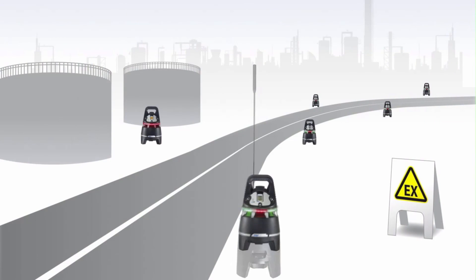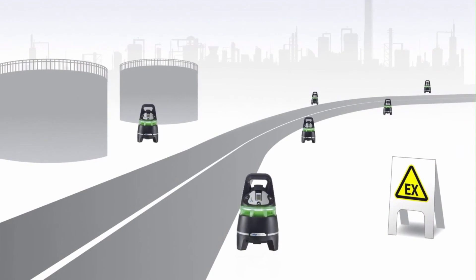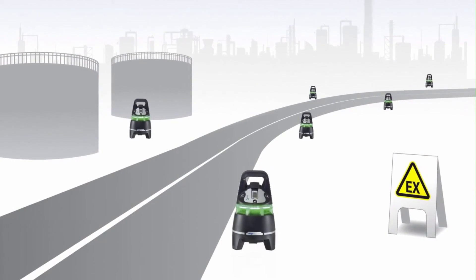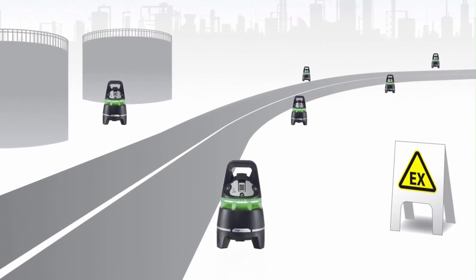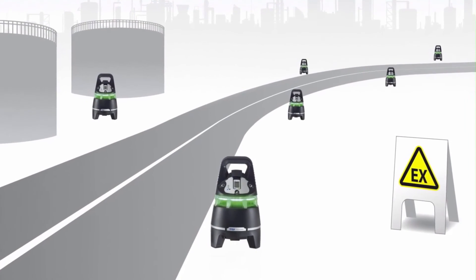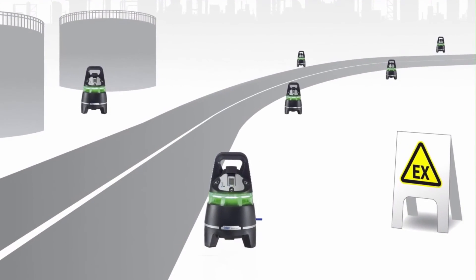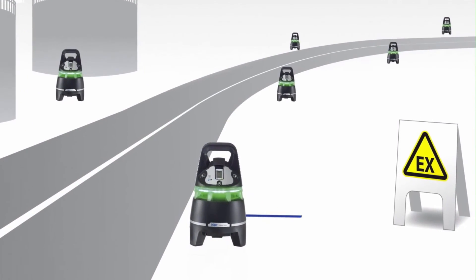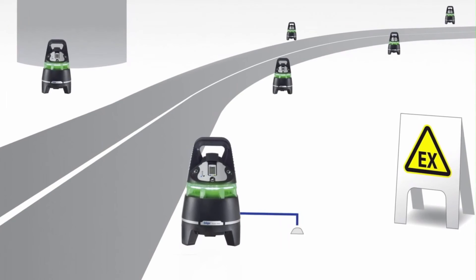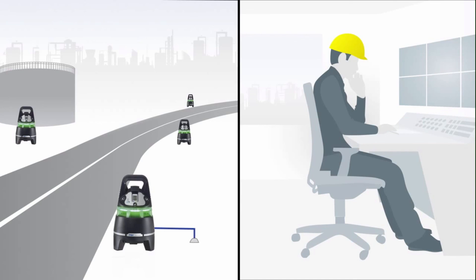You can also integrate X-Zones into your existing gas detection system. Every X-Zone has a Modbus interface. Simply connect the device via Modbus and the measurement data from all area monitors will be transmitted in real time to your control center.